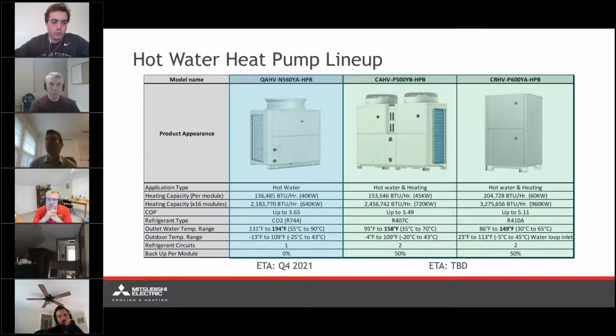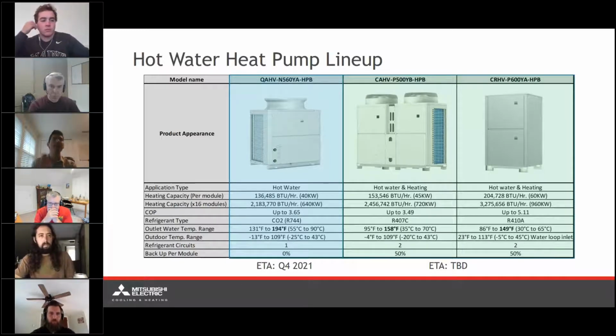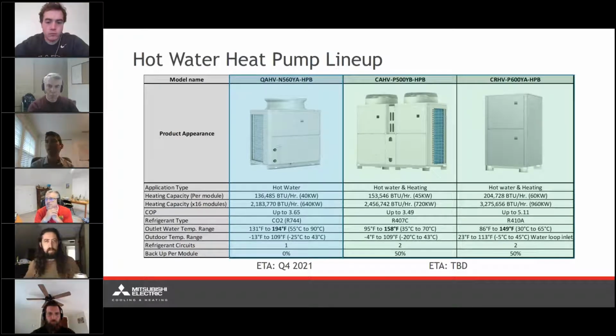All right, so when we're talking about domestic hot water heat pumps, I want to differentiate the options we're talking about here. The lineup we're looking at on the screen is the current European market lineup for hot water heat pumps. The 2 units on the right, in the green, are capable of both domestic hot water heating as well as standard heating like VRF, comfort heating and cooling. That equipment is to be determined for when we're going to be seeing it in the United States. So for the time being, we're only going to be focusing on the QAHV equipment, which is solely a domestic hot water heat pump. There's not going to be separate comfort heating loops off of this.